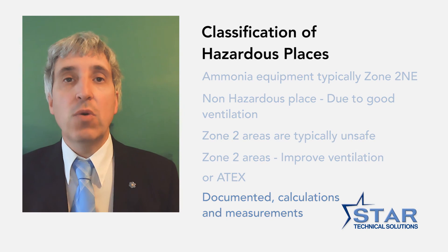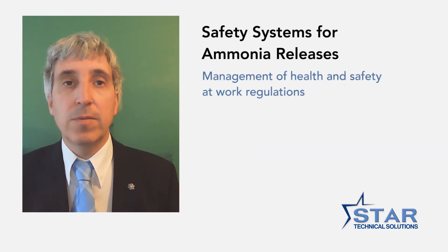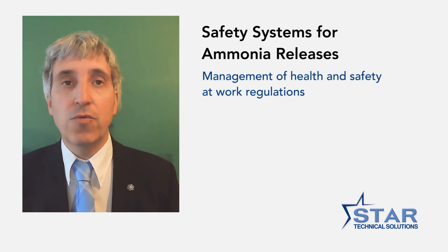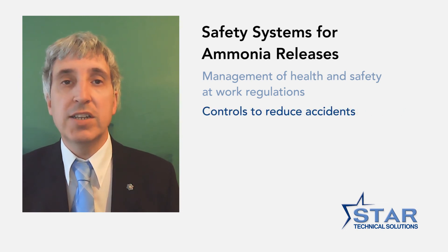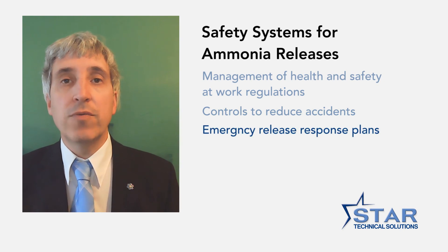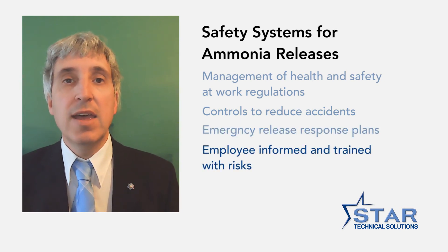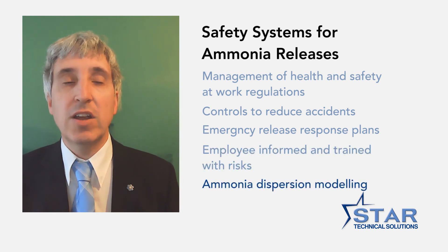There are further requirements in the Management of Health and Safety at Work Regulations 1999. These regulations are very general and for ammonia systems require an assessment of risk due to toxic effects and the effects of skin contact with ammonia. Similar to DSEAR, they require controls to be in place to reduce the effects of an incident involving the release of ammonia. Plans and procedures are to be in place to deal with accidents, incidents and emergencies. Employees are informed and properly trained to control and deal with the risks. Part of the work should include ammonia dispersion modelling to demonstrate that safety systems are adequate.